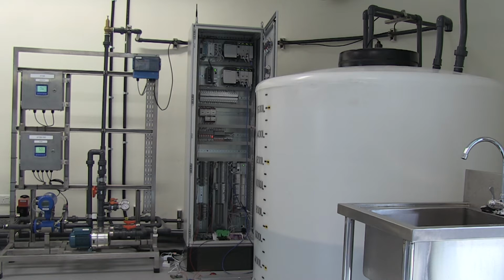All tanks in SWaT carry the same level markings. The level sensor is an ultrasonic level sensor. The water level is transformed into a 4 to 20 milliampere value that is finally digitized to indicate to the PLC the water level in the tank. All tanks are fitted with an ultrasonic level sensor. These are 2 sensors to measure the pH and oxidation reduction potential of the raw water. The measurements are transmitted to the PLC in stage 2.